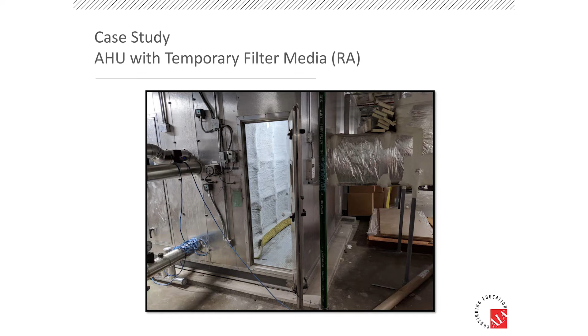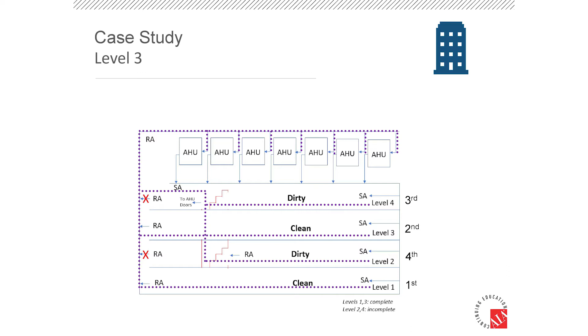So the idea would be, once the test and balance scope of level 1 is done and level 4 is ready for balancing, you do the same thing to level 3. You'd close that stairwell door on 3 and open the return path on that floor, then do the same thing for the other floor.